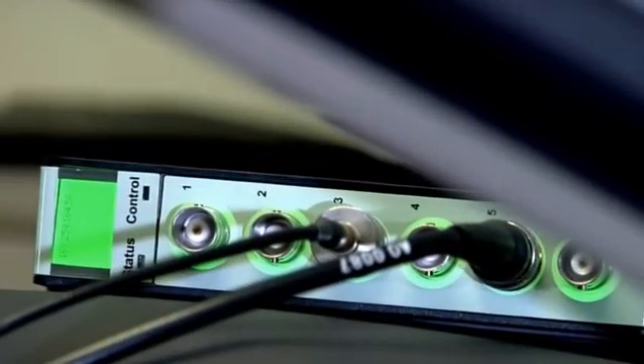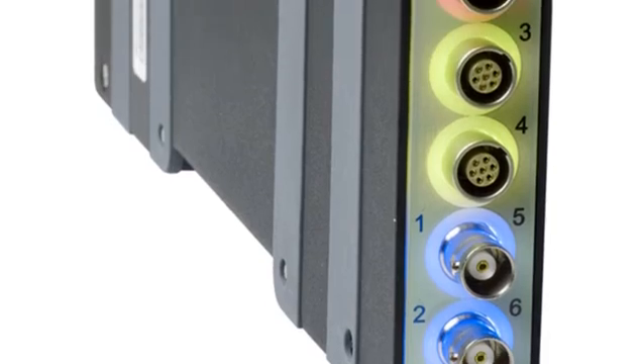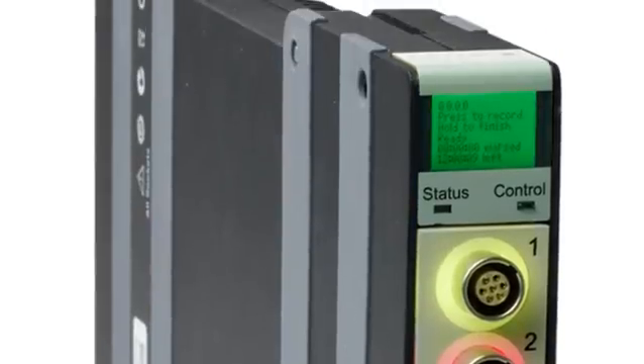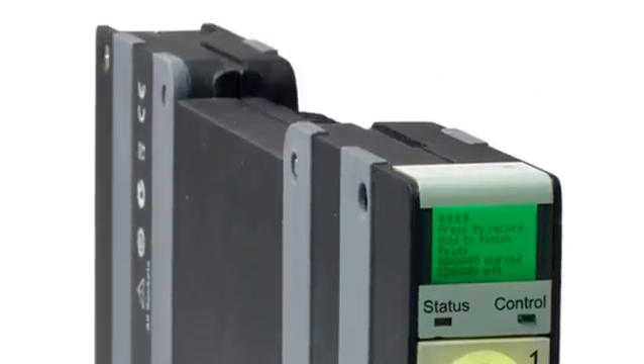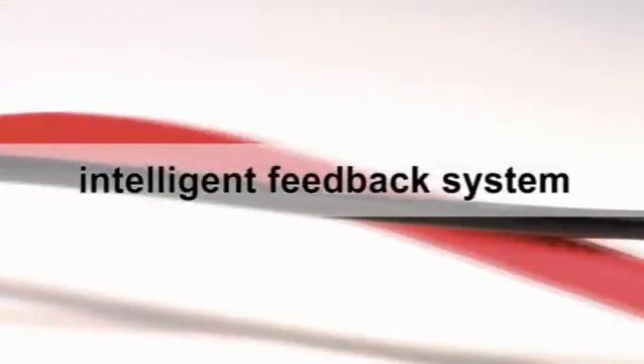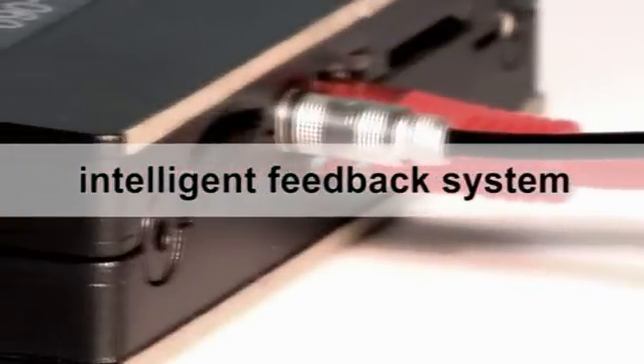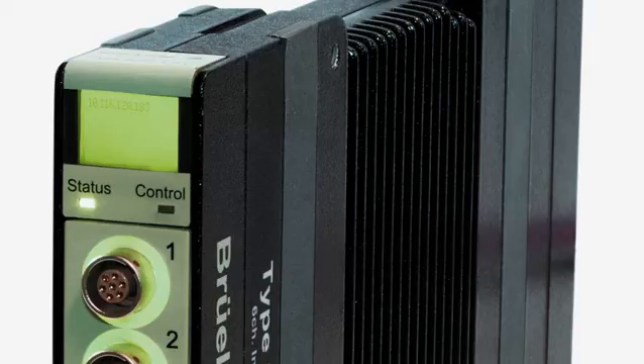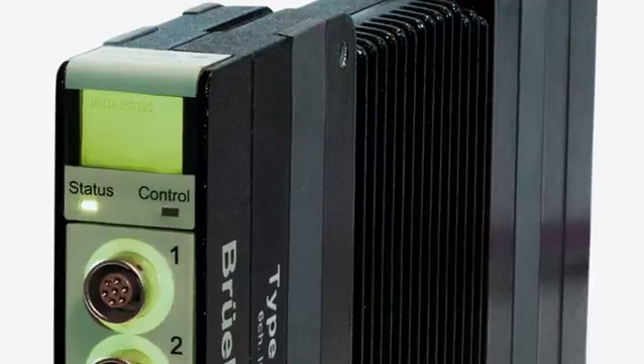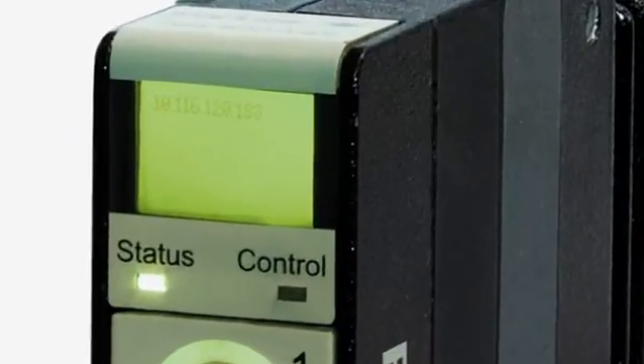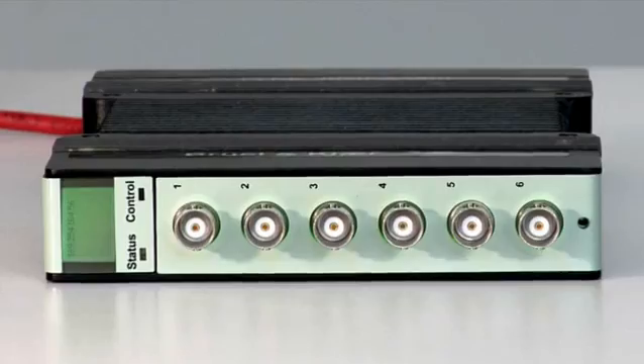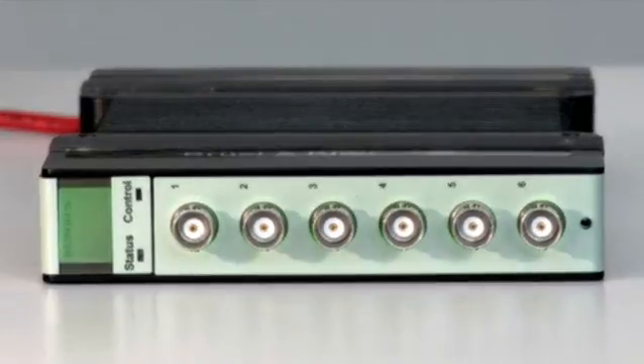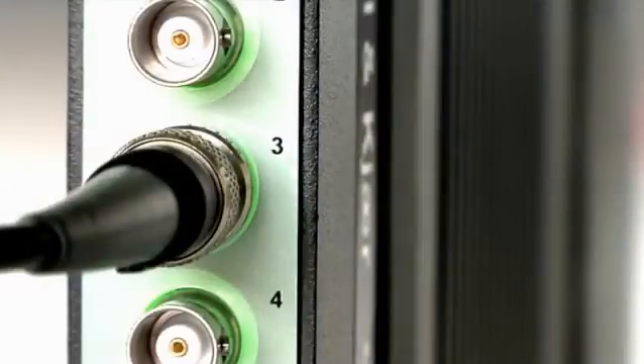With LAN-XI, you also save time troubleshooting. Each module has a built-in intelligent feedback system that provides a quick system status. Is the system running? Is the configuration correct? Are the electronics intact? In other words, faster setup and fewer trial runs. And circular LEDs indicate each connector's condition. For example, a green light indicates an active input channel, and a red light input overload.